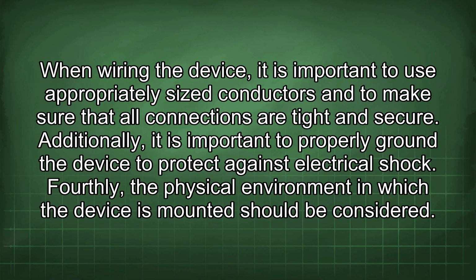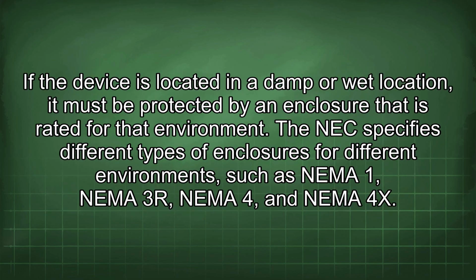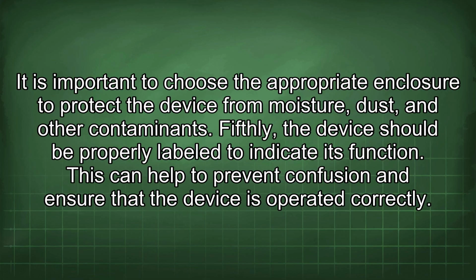Fourthly, the physical environment in which the device is mounted should be considered. If the device is located in a damp or wet location, it must be protected by an enclosure that is rated for that environment. The NEC specifies different types of enclosures for different environments, such as NEMA 1, NEMA 3R, NEMA 4, and NEMA 4X. It is important to choose the appropriate enclosure to protect the device from moisture, dust, and other contaminants.